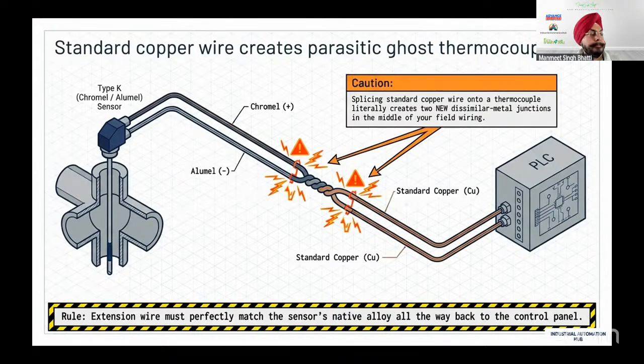The second error is this second mistake that we have. If you see the picture, what happens is, people install the thermocouple in the thermowell, and the two wires are coming out of it. Now, these two wires actually have to go to the cold junction for the measurement, either into a PLC or any controller. So if you see a K-type sensor, we have chromel and alumel coming up. Now, after it comes out of that particular sensor, what we do is, we put a standard copper wire, okay? Standard 2-core shielded and all that stuff. We use that copper wire, and now we take that copper wire back to my PLC. Now, what is happening over here is, you have created another junction for the thermocouple. So we have one junction which is a hot junction, and on the cold junction, again you have added copper, and that copper is again getting added to the PLC, and in the PLC you are measuring it on the thermocouple side.